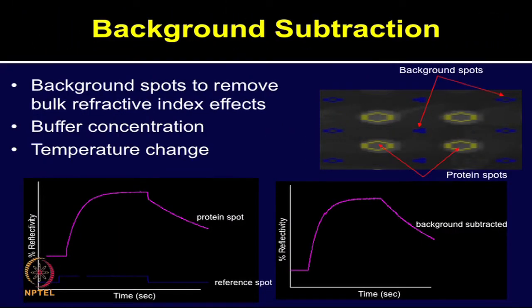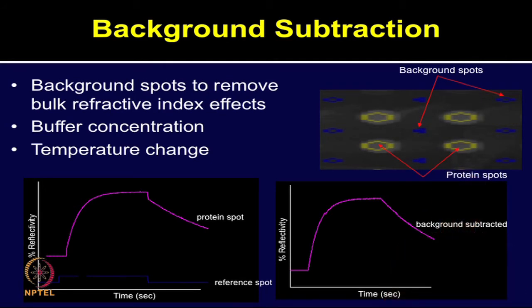The background spots are used to remove the bulk refractive index effects. There are spots of interest and four software-generated background spots. The panel at the top in the slide shows the protein spots with signal, and the blue one represents the reference spot signal. In the graph below, the X axis represents time in seconds and Y axis shows percentage reflectivity. The left-hand side graph shows the non-subtracted curve. When we subtract the reference spot intensity from the protein signal, a background-subtracted signal image is generated, shown in the right-hand side graph.